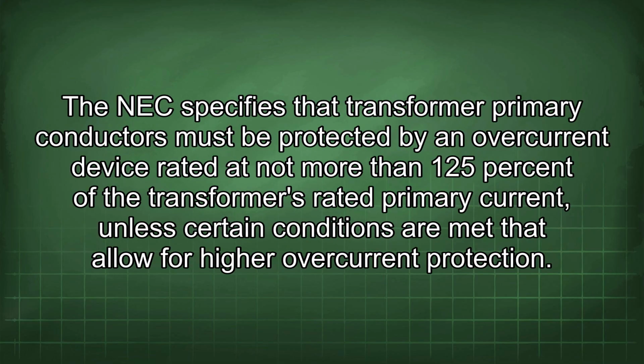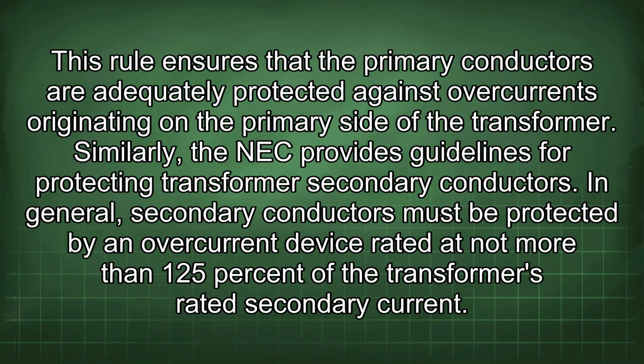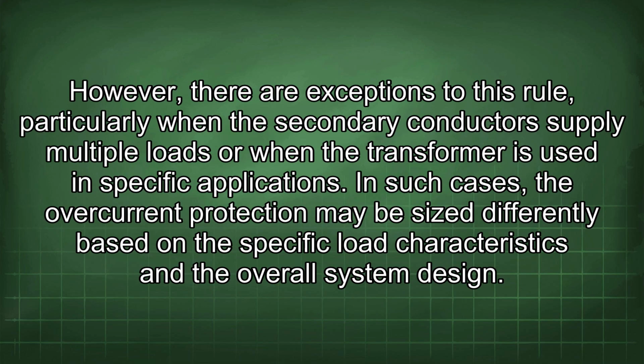requirements. The NEC specifies that transformer primary conductors must be protected by an overcurrent device rated at not more than 125% of the transformer's rated primary current, unless certain conditions are met that allow for higher overcurrent protection. This rule ensures that the primary conductors are adequately protected against overcurrents originating on the primary side of the transformer. Similarly, the NEC provides guidelines for protecting transformer secondary conductors. In general, secondary conductors must be protected by an overcurrent device rated at not more than 125% of the transformer's rated secondary current. However, there are exceptions to this rule, particularly when the secondary conductors supply multiple loads or when the transformer is used in specific applications.